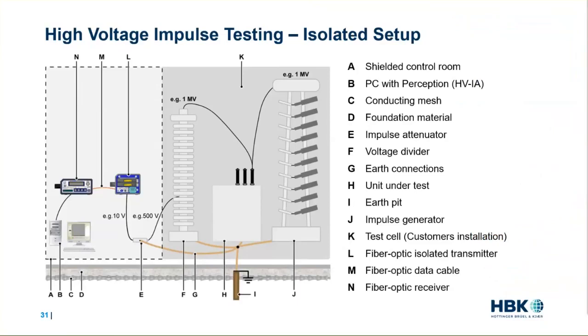Now here you see a test setup starting from the middle of the diagram at the existing lab's voltage divider, labeled F. That's where we then connect to item E just to the left of F, which is the high voltage 50-to-1 impulse attenuator, which is able to accept up to 2,000 volts RMS. And here in this example, the 500 volts at the input is seen at the attenuator, and 10 volts is then at the output, which is connected to L just above E, which is a battery-operated, high-voltage, fiber optic isolated digitizer, or transmitter, which is going to output the fiber signal on the cable M, as in Mary, to the fiber optic receiver, N as in Nancy, which is connected to B, the PC running the software for control and analysis of the impulse test.